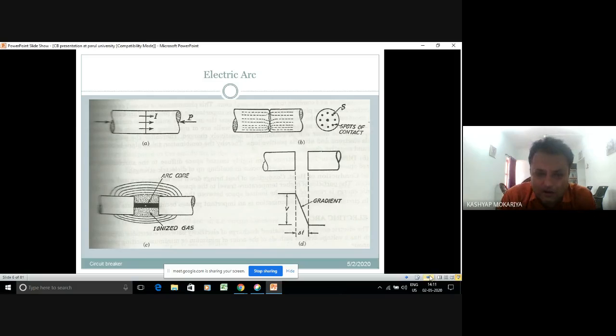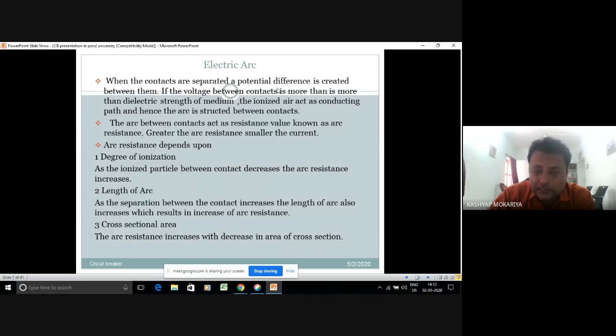Or an air circuit breaker: when the contacts are separated, the arc will be formed like this. The reason is that when the contacts are separated, a potential difference is created between them. If the voltage between contacts is more than the dielectric strength of the medium, the ionized air acts as a conducting path, and hence the arc is struck between the contacts. The arc between contacts acts as a resistance known as the arc resistance. The greater the arc resistance, the smaller the current. It depends on the degree of ionization: as the ionized particles between the contacts decrease, the arc resistance increases.